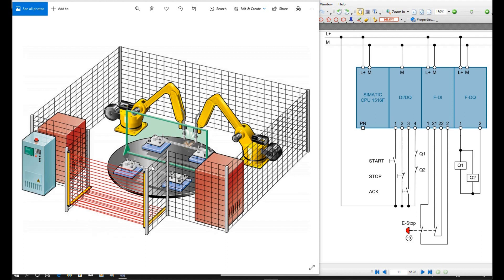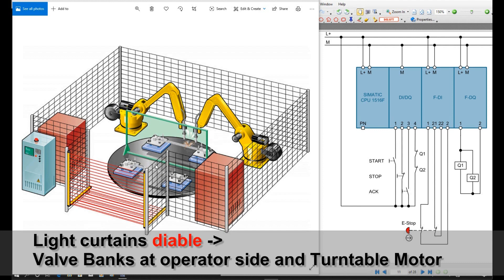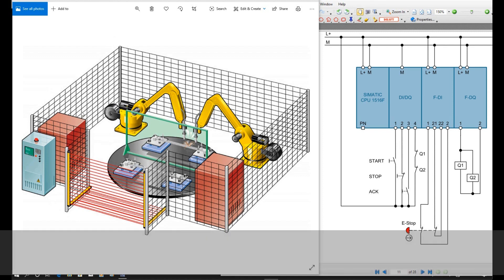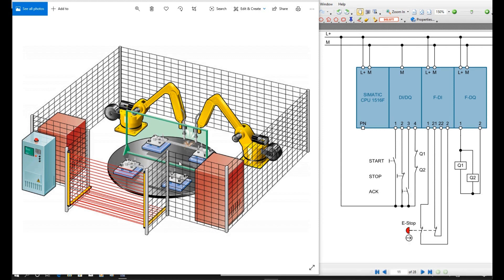For this turntable and the robot, the safety logic control would be a little bit different. For example, for the light curtain, if the light curtain breaks, the valve control and the turntable control should be disabled. But the actuators in the cell, for example the robot and the valve bank inside the cell, while they're working, actually they don't need to care about this light curtain. But if we open this maintenance gate, once the gate opens, the robot and all the valve banks should be disabled.